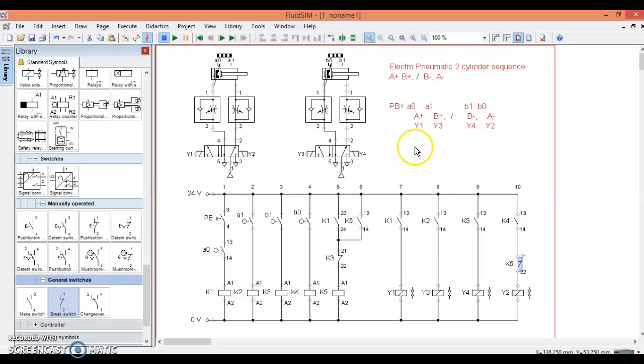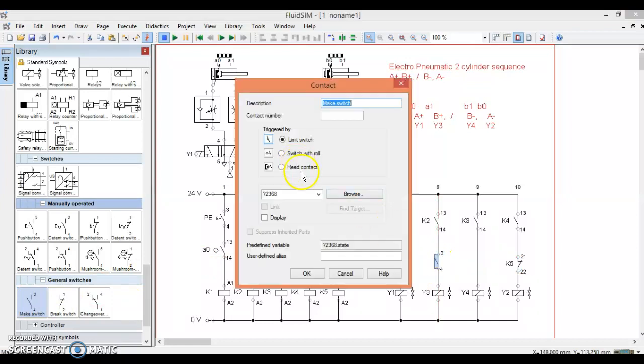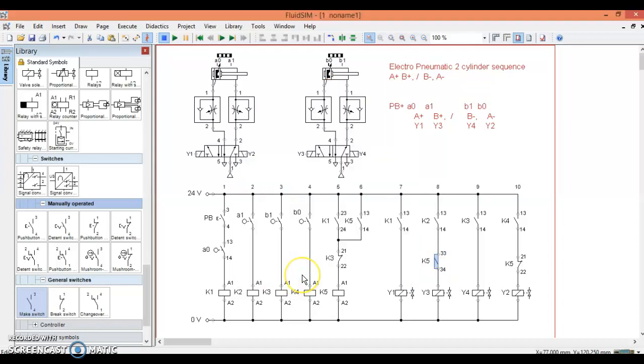We then also have an issue here, where we want Y3 to be able to activate, but Y4 will already be active in the middle part. So what we do is we drop in a normally open element from K5 here. So now we've interrupted the elements that we need to interrupt.